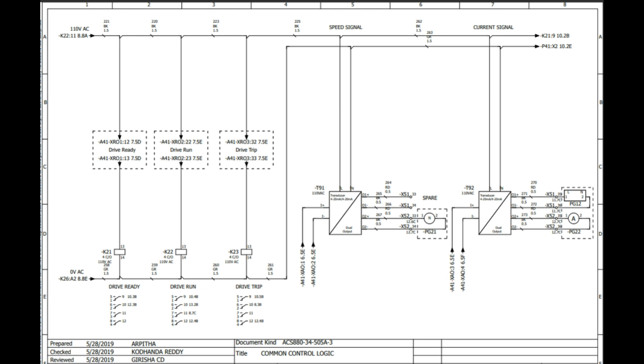See this dotted box, what is written here. You can compare with the previous slide. You will get to know the proper idea: when the drive will run, when the drive will trip, and when the drive will show the ready command. Next we'll come to the half section of this page, that is the speed signal and current signal.